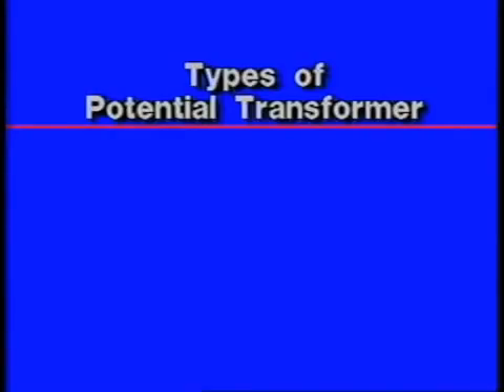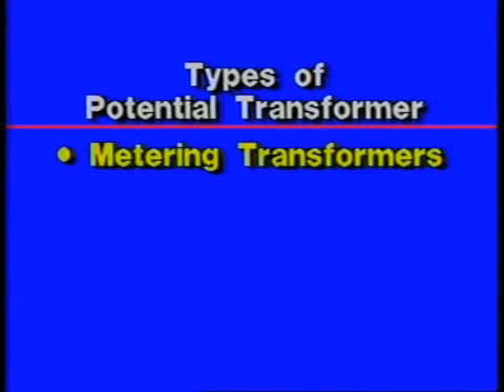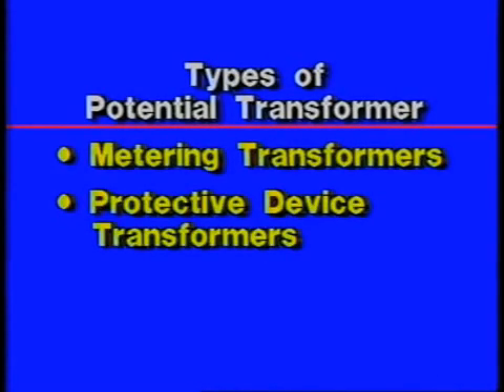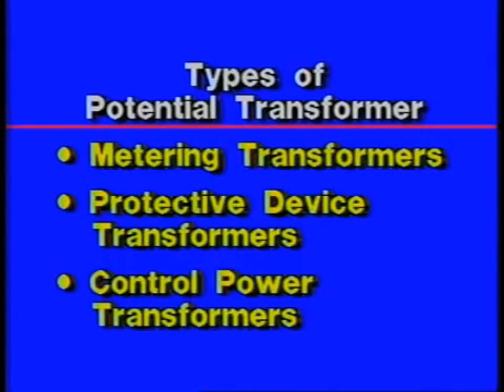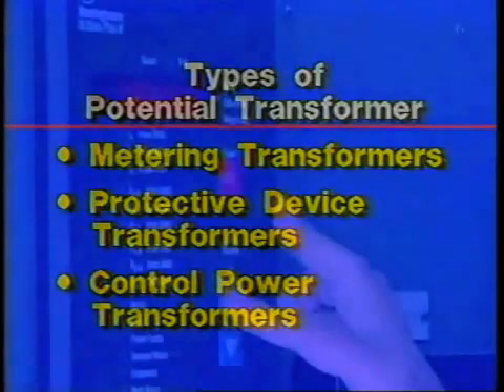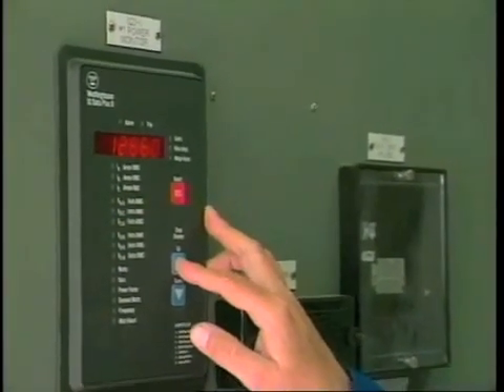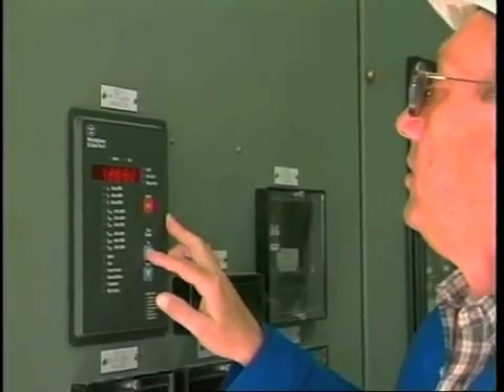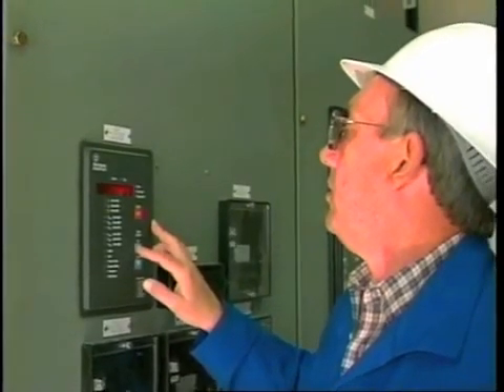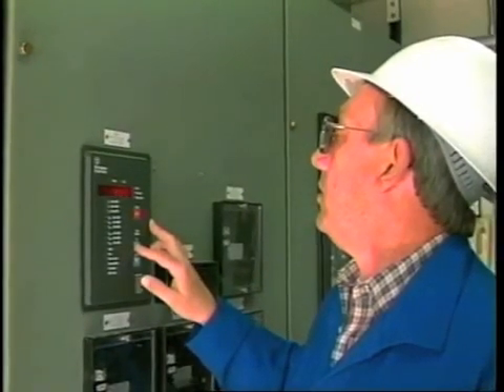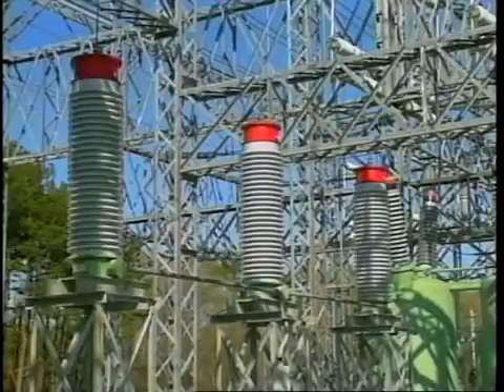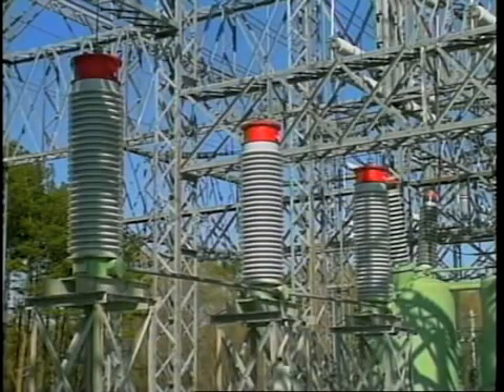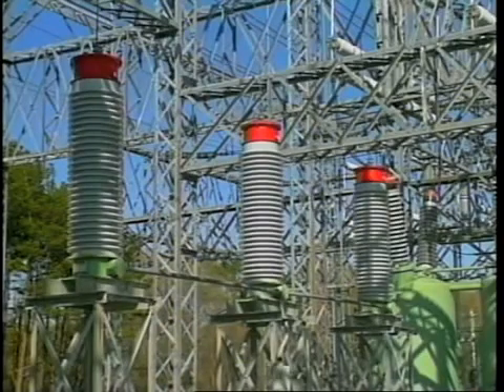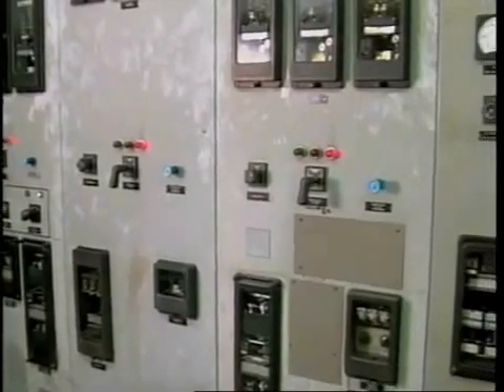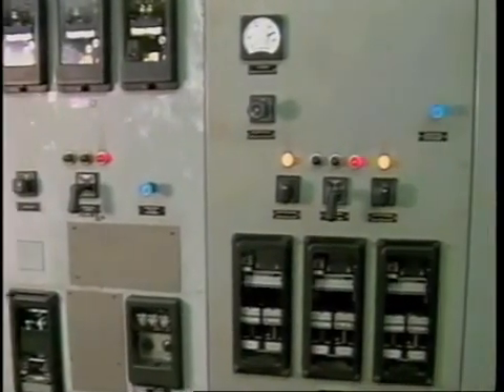There are 3 types of potential transformers: metering transformers, protective device transformers, and control power transformers. Metering transformers are used for very precise measurement of voltage. Electrical utilities depend on these metering transformers for determining power flow through a particular commercial circuit. Protective device transformers do not require the precision of metering transformers. A common application of protective device transformers is to provide a low-voltage source for protective relay operation and metering where accuracy is not critical.